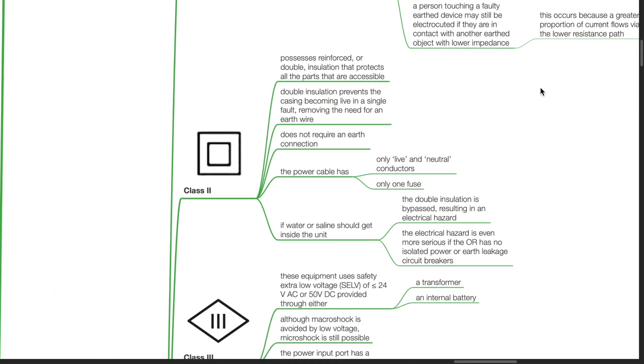Class 2 equipment possesses reinforced or double insulation that protects all accessible parts. Double insulation prevents the casing becoming live in a single fault, removing the need for an earth wire. There is no need for earth connection; the power cable has only live and neutral conductors and only one fuse. If water or saline gets inside the unit, the double insulation is bypassed, resulting in an electrical hazard that is even more serious if the OR has no isolated power or earth leakage circuit breakers.